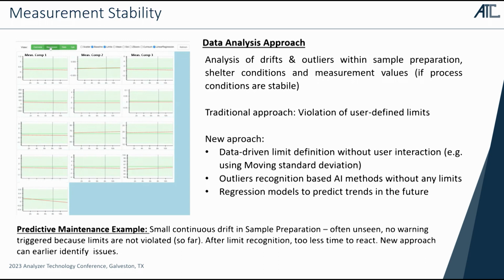We have used that to solve an issue of continuous small drift within the sample preparation. We had a loss of pressure here. The pressure was always between the limits, but it was decreasing over time. In the past, the issue was that you had to wait until the limit was violated, but that was a problem because you might already have an issue. In this case, the software can tell you, I see a drift here, you should look into the sample preparation, and you can act far earlier and solve that issue.